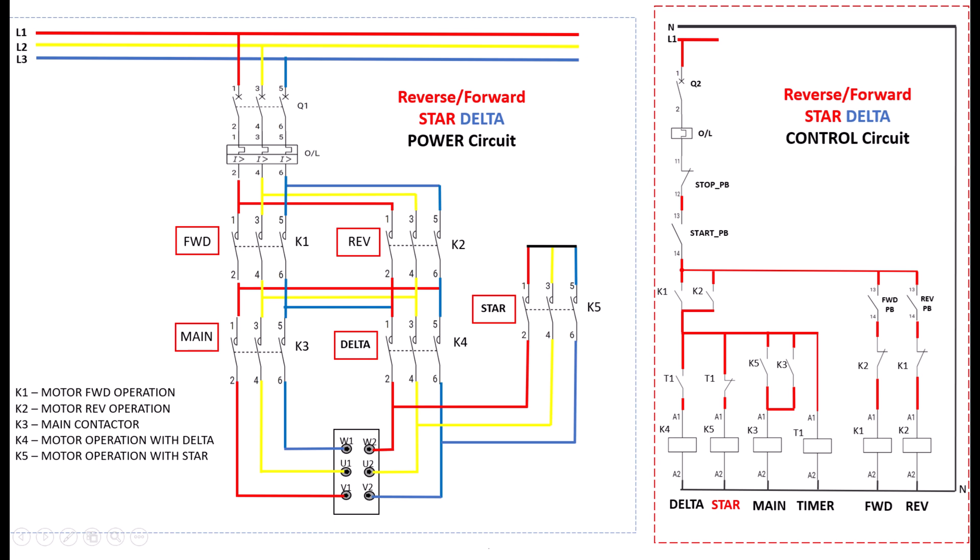The star delta starter is a widely used system in industries, primarily because of its ability to reduce starting current, which helps prevent high inrush currents that could otherwise damage the motor. It also provides directional control, enabling motors to operate in forward or reverse directions depending on application requirements. Additionally, the smooth transition from star to delta mode ensures efficient and safe operation, especially for heavy machinery, making it an essential component in industrial motor control systems. Now, let's talk about the core components.